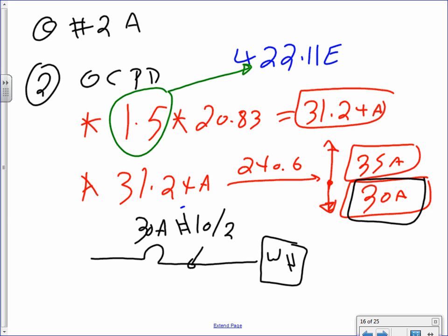Could I have gone to 35? Yep. What do you need to do if you go 35? Then you have to change your conductor to number 8. You're allowed to go to 35. You don't have to go to 35. There's a difference between allowed to and have to.